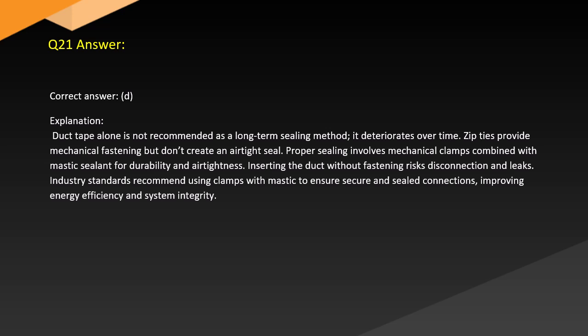Answer. Correct answer, D. Explanation. Duct tape alone is not recommended as a long-term sealing method. It deteriorates over time. Zip ties provide mechanical fastening but don't create an airtight seal. Proper sealing involves mechanical clamps combined with mastic sealant for durability and airtightness. Inserting the duct without fastening risks disconnection and leaks. Industry standards recommend using clamps with mastic to ensure secure and sealed connections, improving energy efficiency and system integrity.